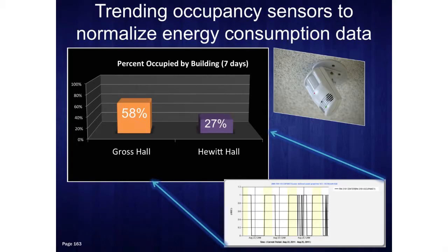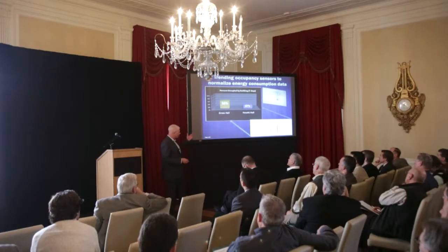Trending of occupancy sensors. Everybody says their labs are occupied all the time. Maybe that's true, maybe that's not true. But isn't it interesting to trend the EUI versus the occupied hours of a space, right? So yes, that's energy intensive, but are they ever there? Those kinds of questions, they can all be answered here.